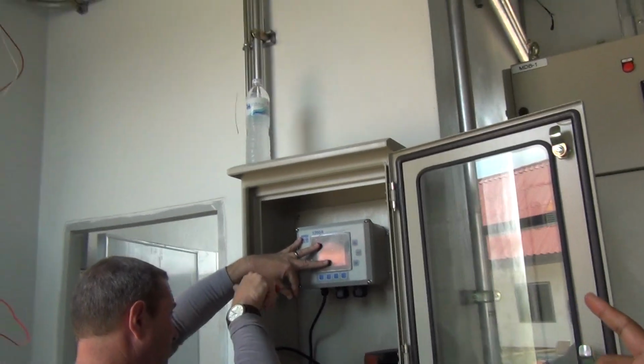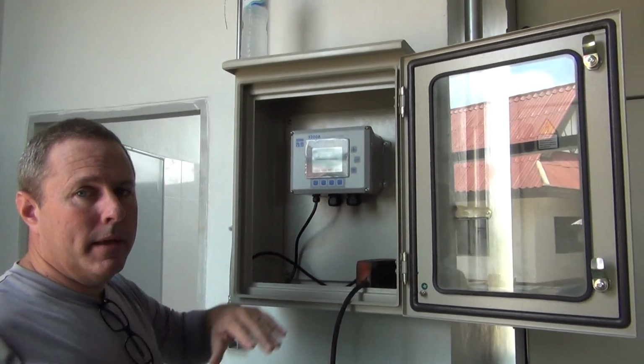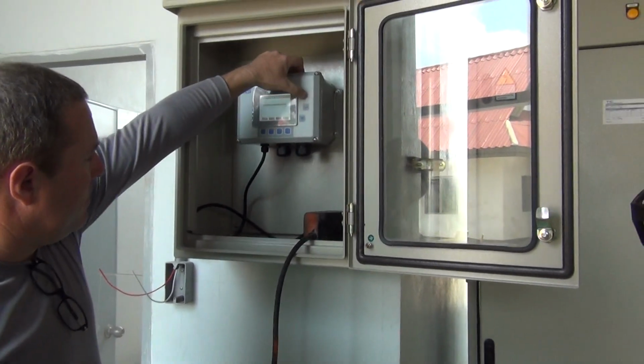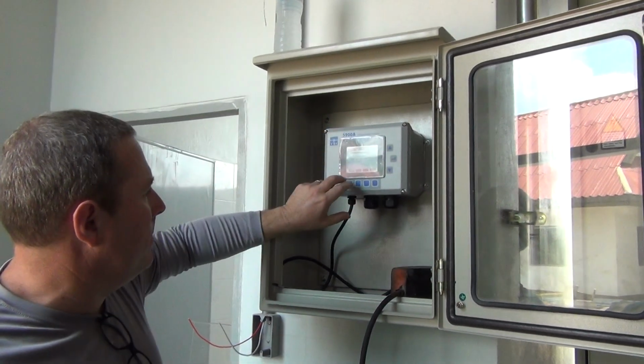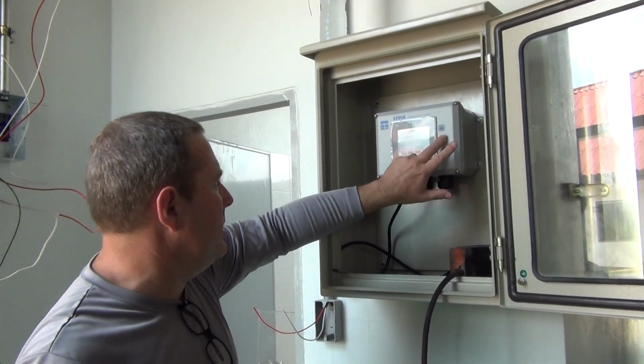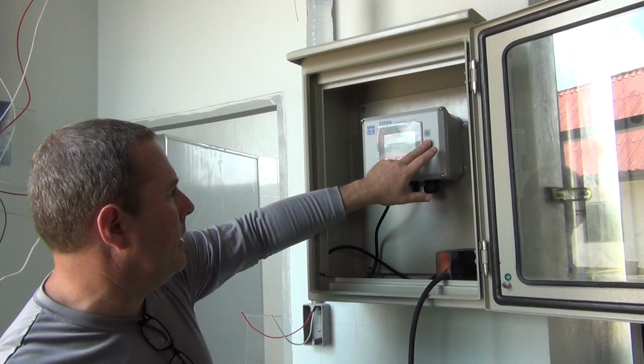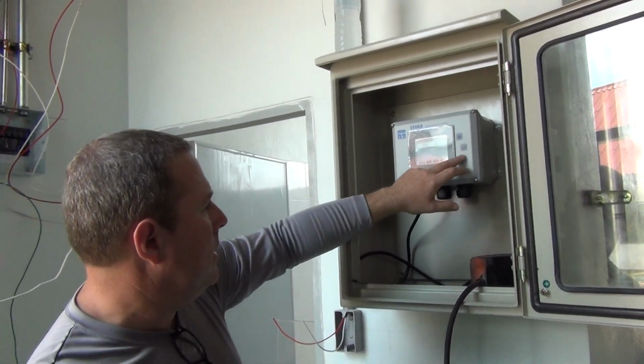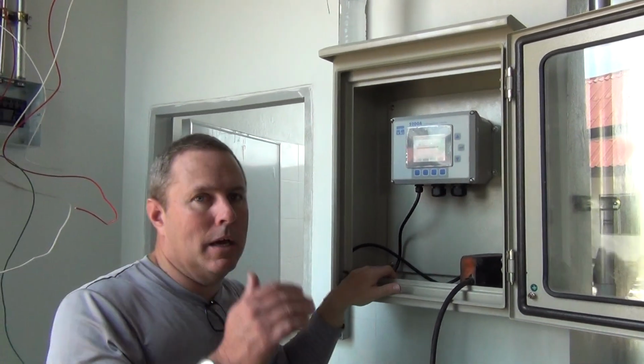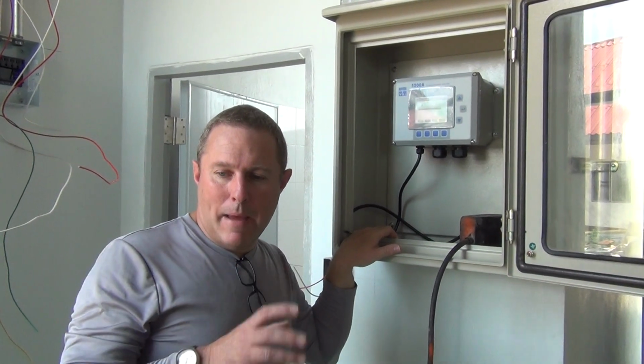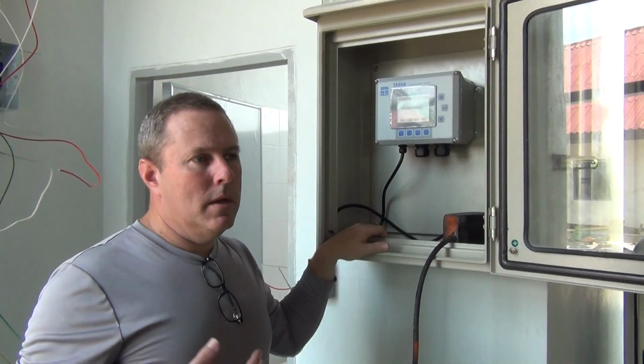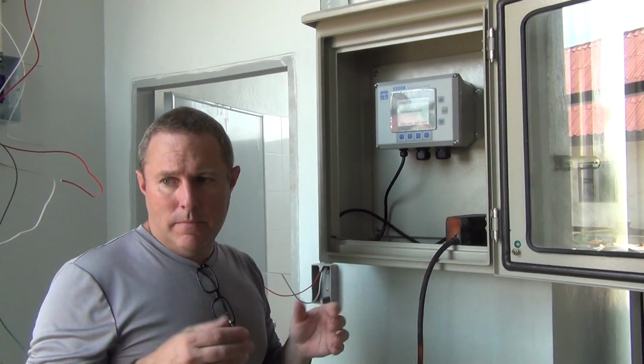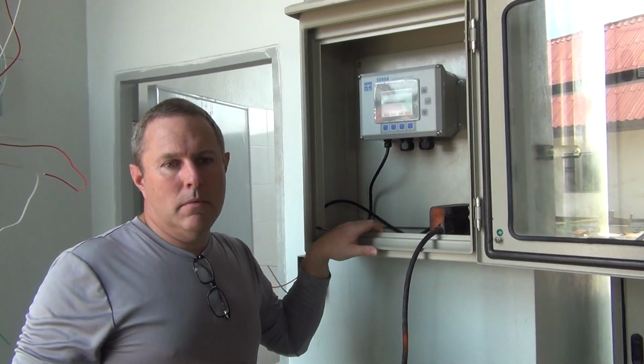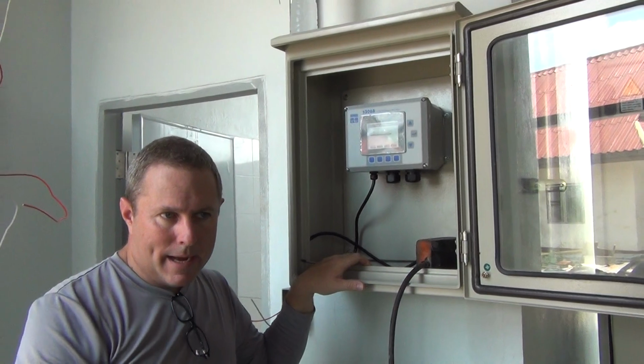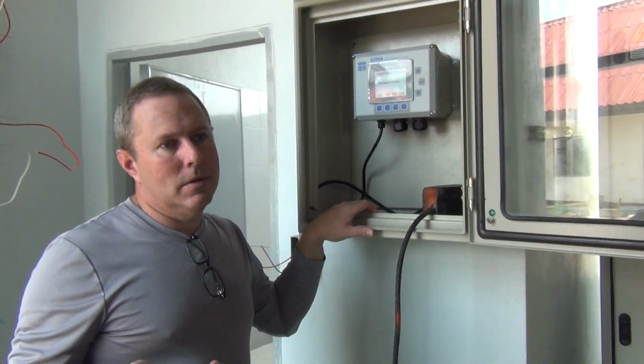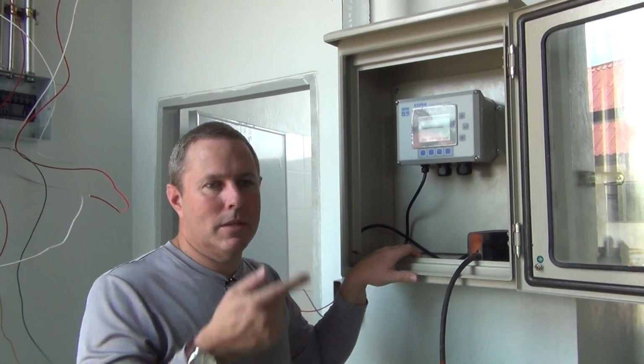But once you have a low voltage power supply for battery backup, then we would simply come in here and set up power fail system enable, and then AC enable. Battery monitor would be enabled. And then what is the voltage of the battery when it's low? So that it tells you if the backup battery is low. It's saying 15 volts, because a normal 12 volt battery is a little higher than that, but I would say lower. But that will send a message if the battery backup voltage drops. So maybe if it gets to 11 or 12 volts, it sends a message that there's a problem.